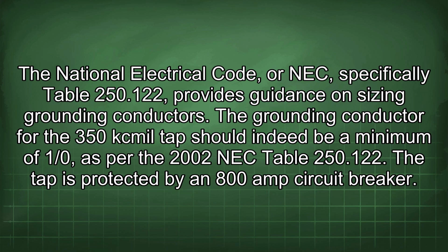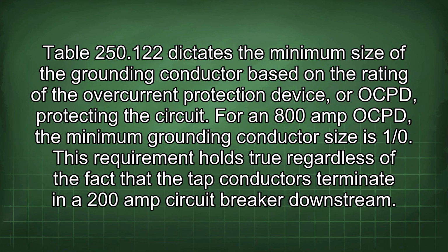The grounding conductor for the 350 kcmil tap should indeed be a minimum of 1/0, as per the 2002 NEC Table 250.122. The tap is protected by an 800 amp circuit breaker. Table 250.122 dictates the minimum size of the grounding conductor based on the rating of the overcurrent protection device, or OCPD, protecting the circuit. For an 800 amp OCPD, the minimum grounding conductor size is 1/0. This requirement holds true regardless of the fact that the tap conductors terminate in a 200 amp circuit breaker downstream.